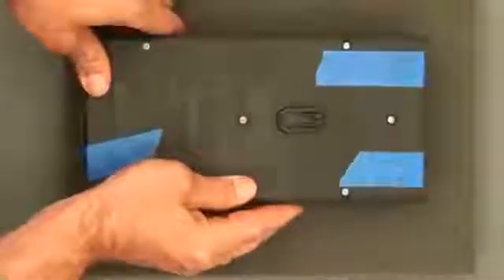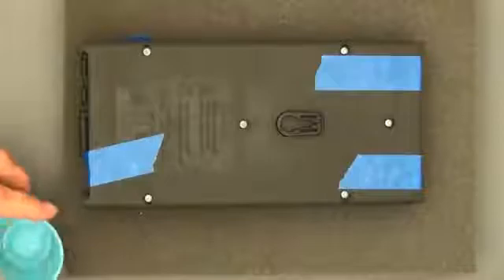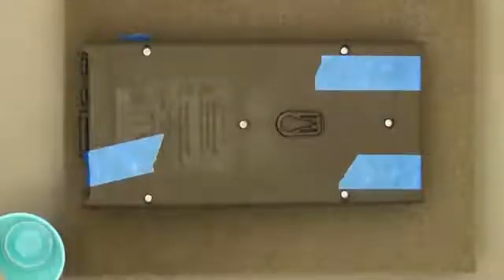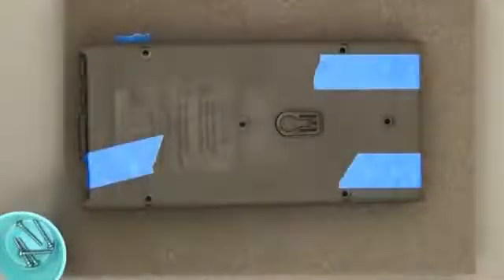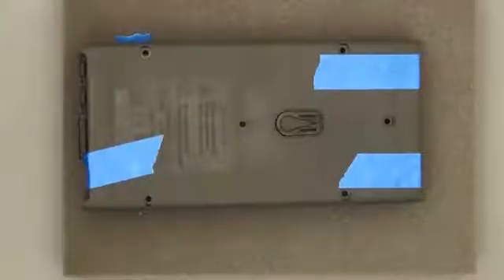Turn over the PEL and locate the 6 fastening screws on the back of the instrument. Using the Torx T10 screwdriver, remove these fastening screws. Carefully separate the front cover of the PEL from the back cover. Typically, the two covers fit together very snugly, so it may be difficult at first to separate them.